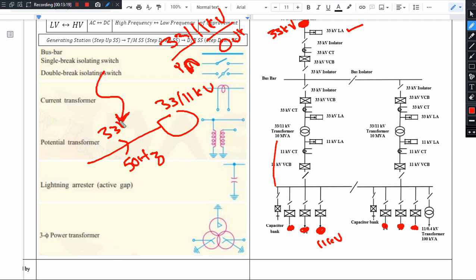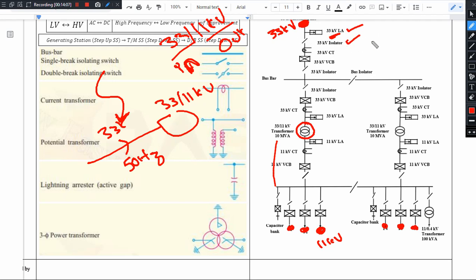After the lightning arrestors, we have a 33 kV isolator switch — an AB switch — for the switching arrangement. Then we have current transformers and vacuum circuit breakers, though these are optional for a 33 by 11 kV substation. For higher setups like 132 by 33 kV, more equipment is warranted. At 33 kV, instead of circuit breakers, we often go for HG fuses — horn gap fuses — which have a horn gap arrangement for arc extinction.